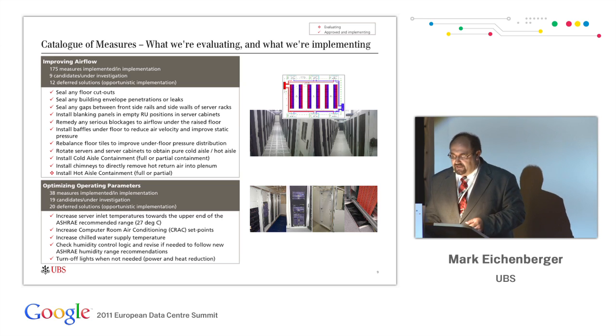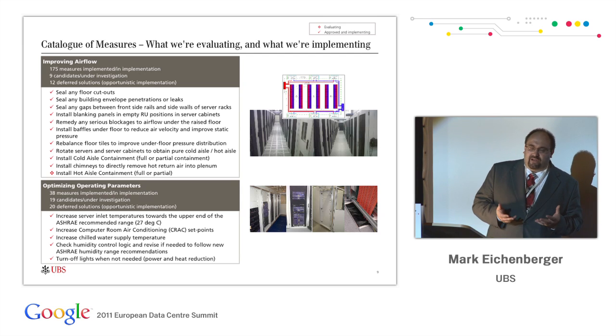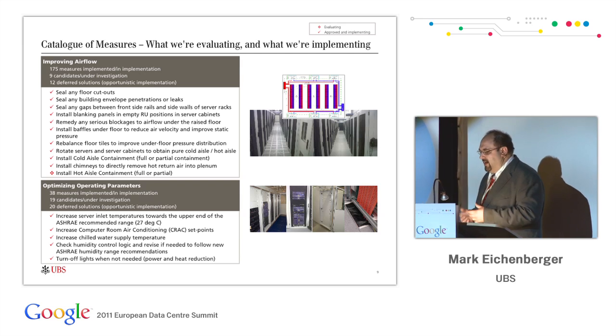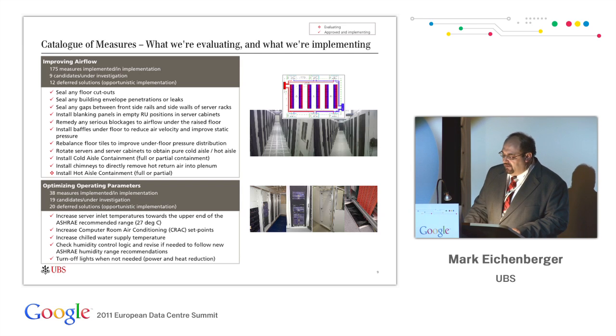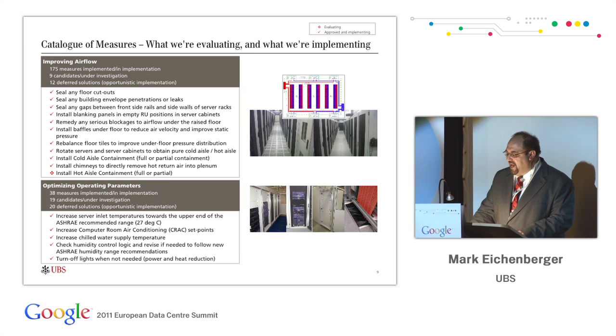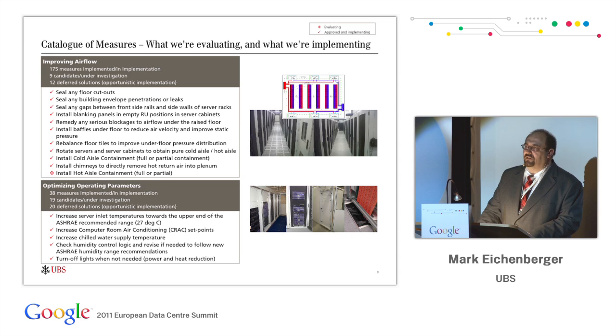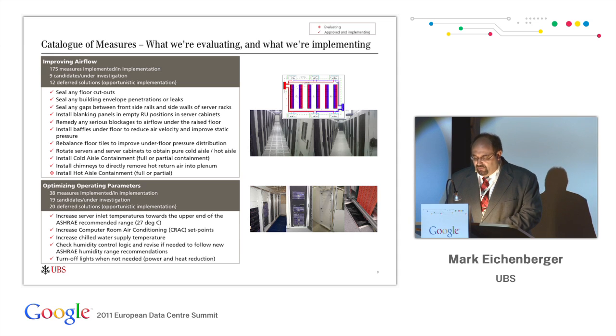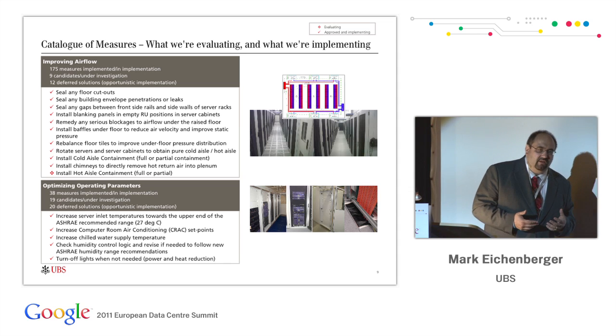And when you look at what we were able to achieve, right? By room, that's a 300 square meter room, with 350 servers running in there, we were able to achieve savings of around 80 to 90% on the operating costs, just from being able to control and reduce the downflow units, the CRACs, within the room. That's astounding. So that was really one of the areas that we'll focus on. We'll start now rolling this out slowly but steadily.